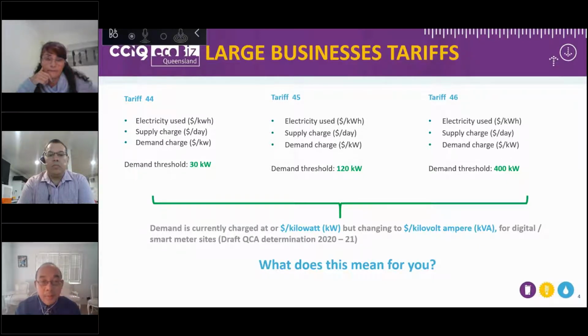Currently, a large customer's most common tariffs are tariffs 44, 45, 46. Each of these tariffs has a demand component, but the demand component is currently calculated on a kW or kilowatt basis. Based on the Queensland Competition Authority, or the QCA, their draft determination for 2020-21, we will have a new option to charge on a kVA basis, initially for digital or smart metered sites.